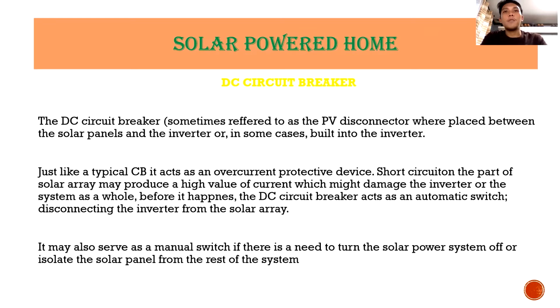It also serves as a manual switch if there is a need to turn the solar power system off or isolate the solar panel from the rest of the system. So, a DC circuit breaker is an OCPD that protects electrical devices operating with DC and contains additional arc extinguishing measures. DC circuit breakers are relatively new technology to most homeowners, since most devices used in the house work in AC.